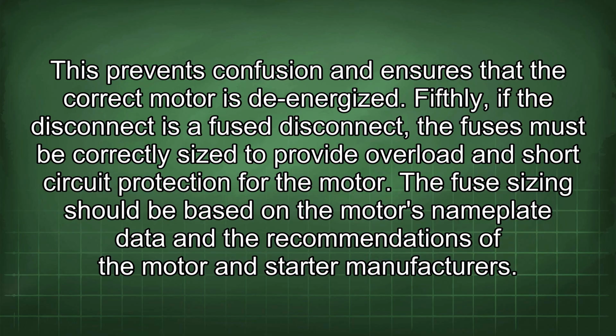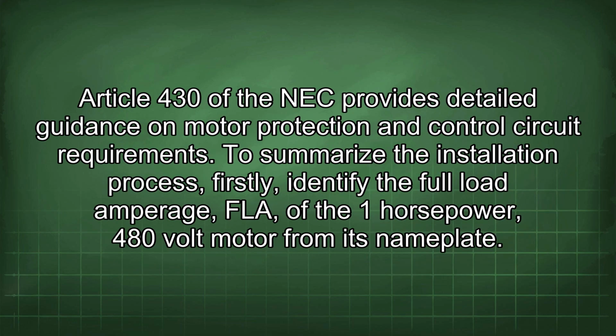Fifthly, if the disconnect is a fused disconnect, the fuses must be correctly sized to provide overload and short circuit protection for the motor. The fuse sizing should be based on the motor's nameplate data and the recommendations of the motor and starter manufacturers. Article 430 of the NEC provides detailed guidance on motor protection and control circuit requirements.